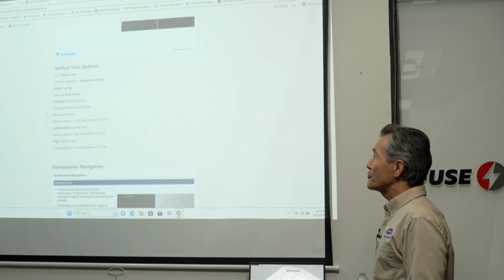So that's why there's an option in here, going to dealer edit. You punch in all 4 digits, equipment setup, begin setup, and choose heat pump. On heat pump you can do heating or cooling, they're separate, heating setup and cooling airflow trim, or it will be heating airflow trim. You can do it on 3 speeds.